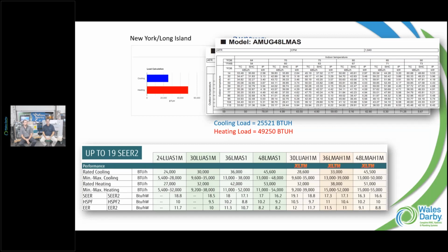On a 70-degree day, we probably need less than 20,000 BTUs for cooling, but we've got a 4-ton system. What's nice about an inverter is that we can ramp down and still maintain temperature. This system will perform great electrically all summer long, because we don't have to ramp up more than 50% of our capacity, probably most of the summer. So the electrical usage of that machine is going to be very low. But we're not going to run that much, so we're not going to pull humidity out of the home, and that's where we're seeing a lot of those problems. And Jeff, I think you made a comment about the humidity as well.